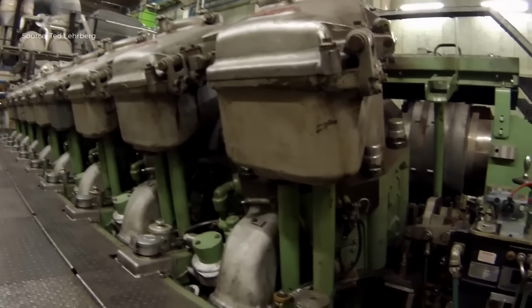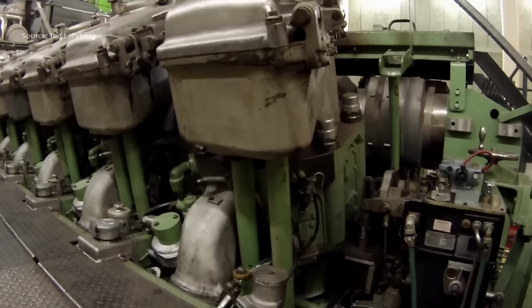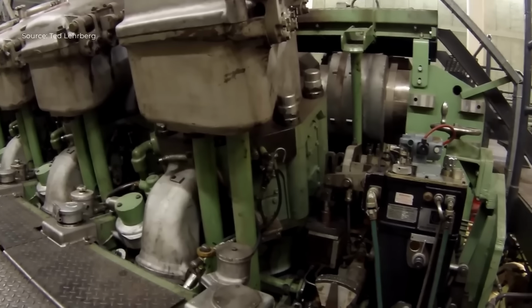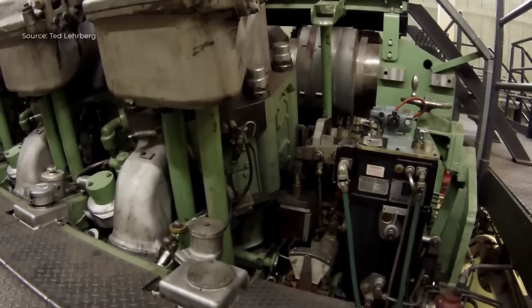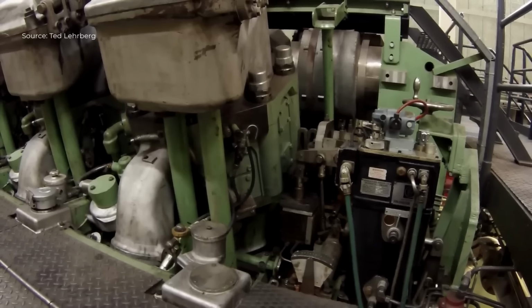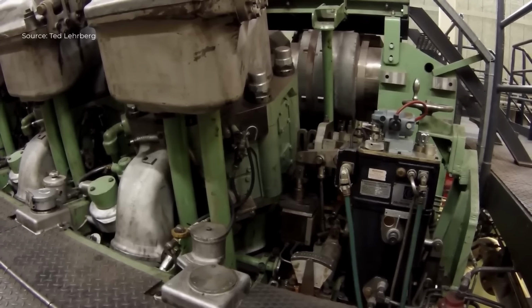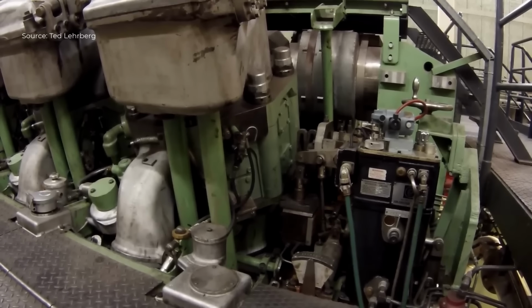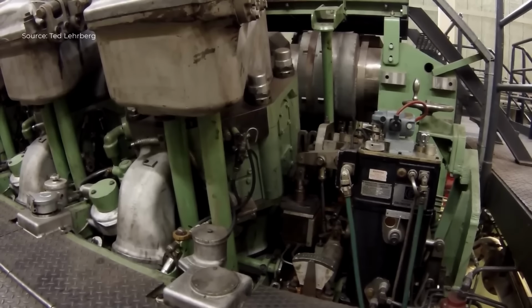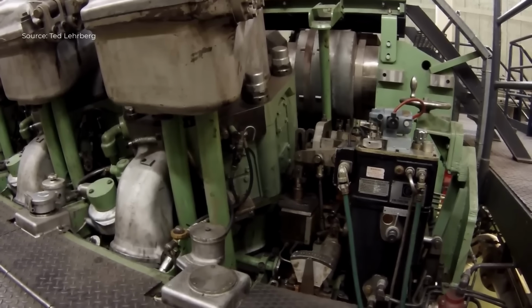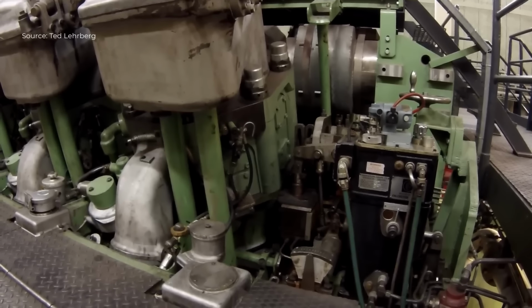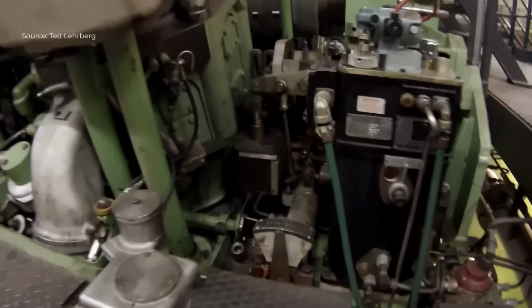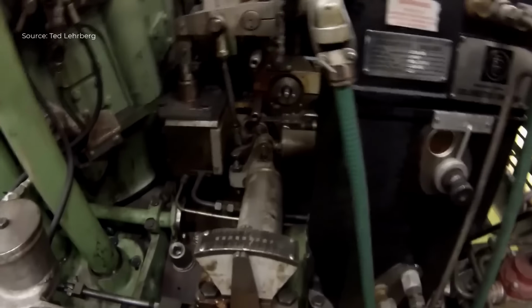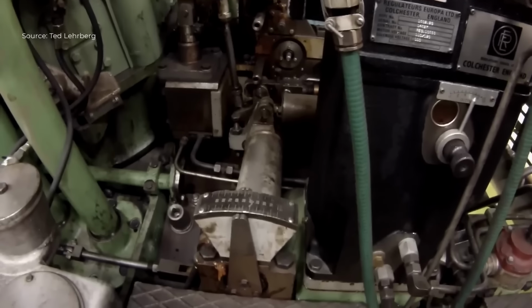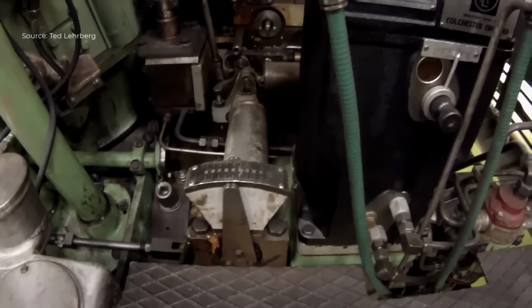After about 1 hour of operation, the load is progressively increased. The engine output is raised to 60 to 70% of the maximum load, which in this case corresponds to a plant capacity of up to 20 megawatts. This step verifies the engine's ability to handle higher thermal and mechanical stresses while maintaining smooth combustion and stable speed. During this phase, exhaust temperatures, vibration levels, and fuel consumption are carefully observed.